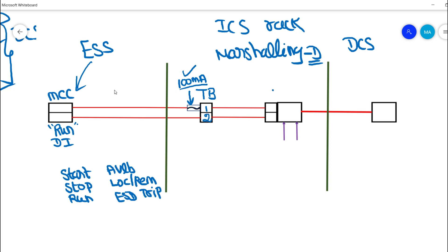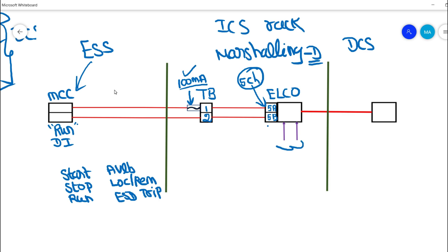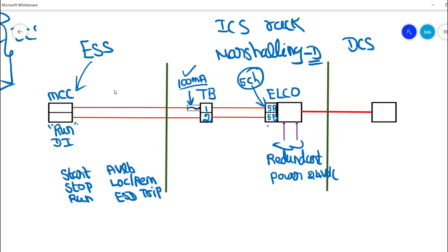From this TB, the signal runs into an ELCO board. I have already discussed the ELCO board in a previous video — you can check it out. In this ELCO board we have digital input channels. In this example I am using channel 5A and 5B — this is the fifth channel in the DCS digital input card. This ELCO board is powered by a redundant power supply, which was covered in a separate ICS tutorial series.